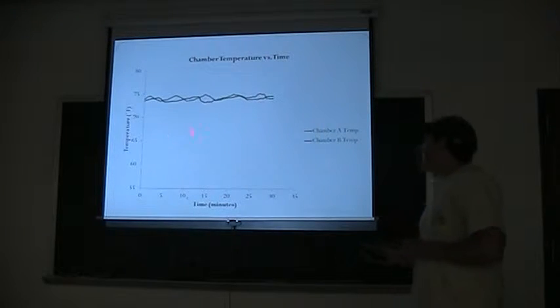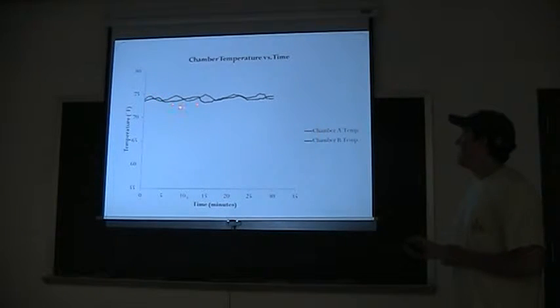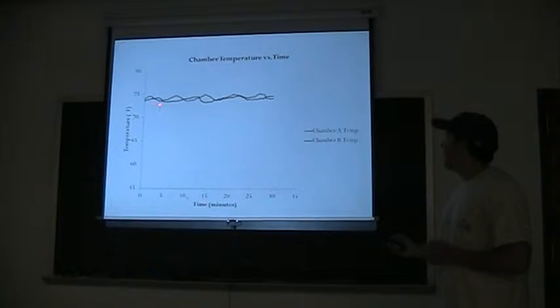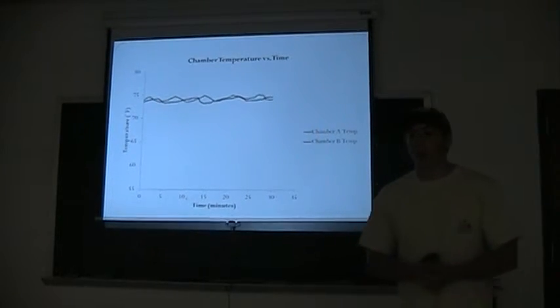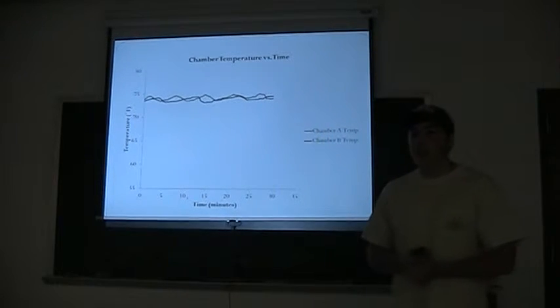If you look at this chart, our set point was about 74, and the supply air temperature was about 55, so each VAV box pretty much just oscillated around each other. They just took over and made sure that the set point stayed pretty neutral.